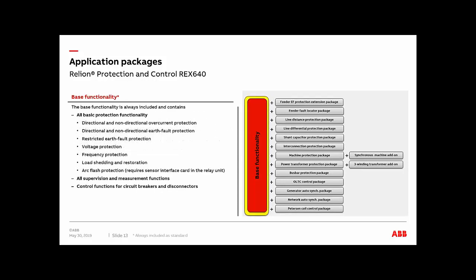So let's talk about the base functionality here. When you select the base relay, even if you don't have any packages in there, you're always going to get your directional and non-directional overcurrent protection. You're going to get directional and non-directional ground fault as well, restricted earth fault. There's voltage protection, frequency, load shedding and restoration is available, and you get our arc flash protection, which requires, of course, that you order your sensor interface for the relay.